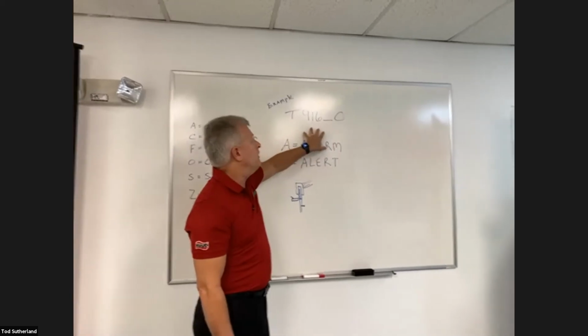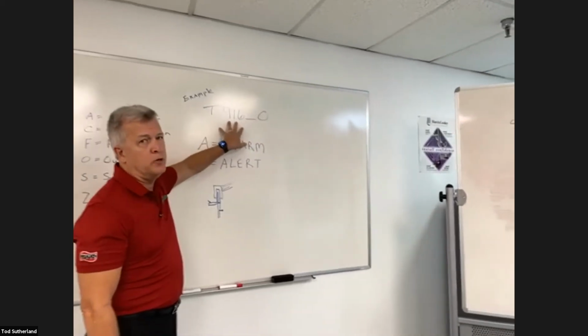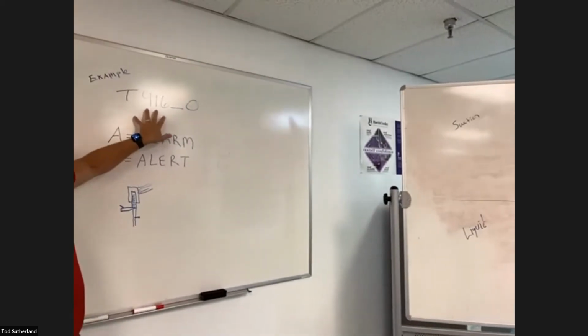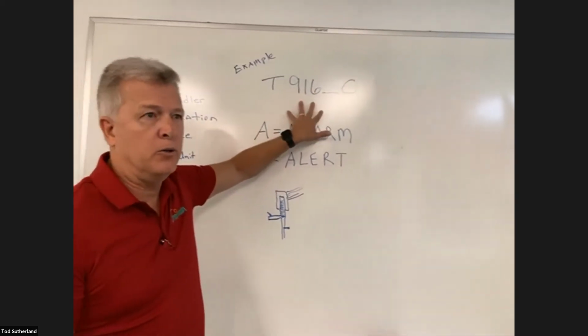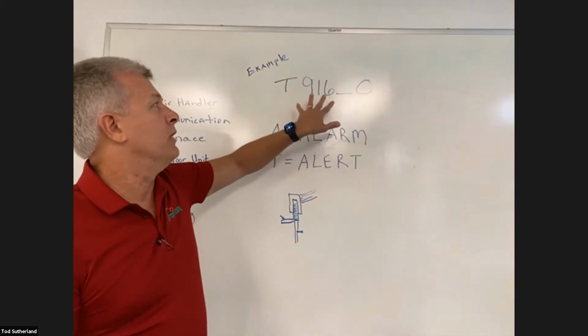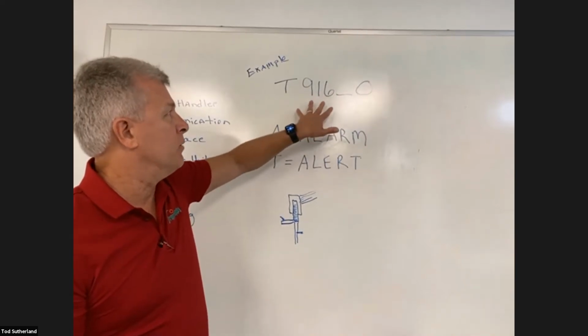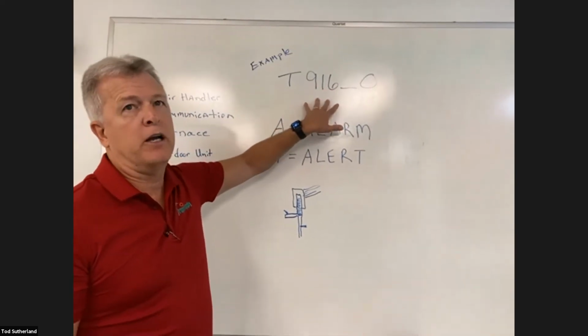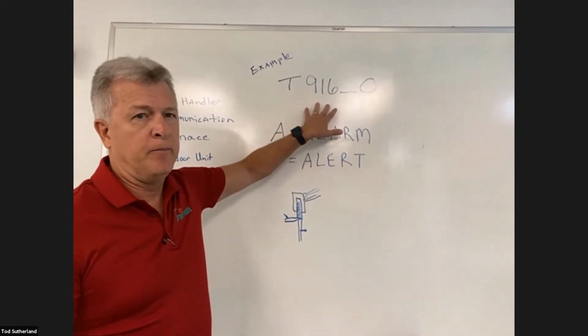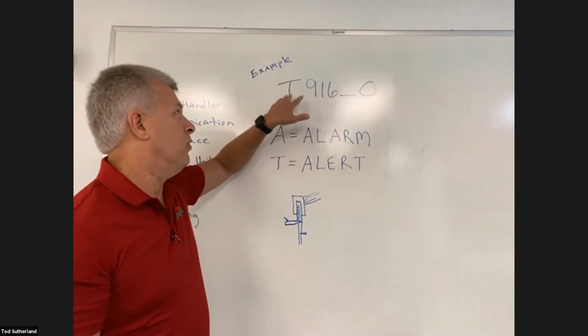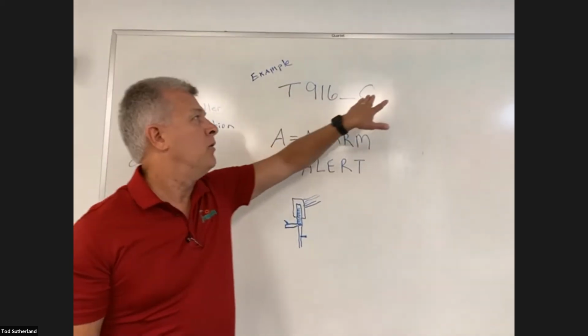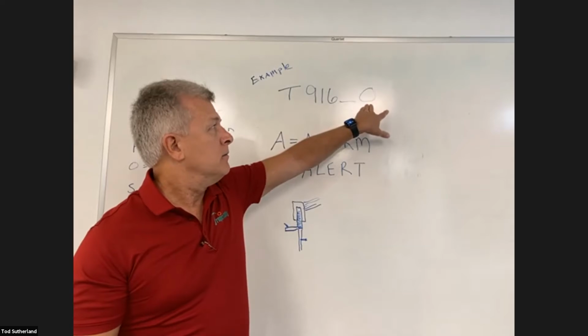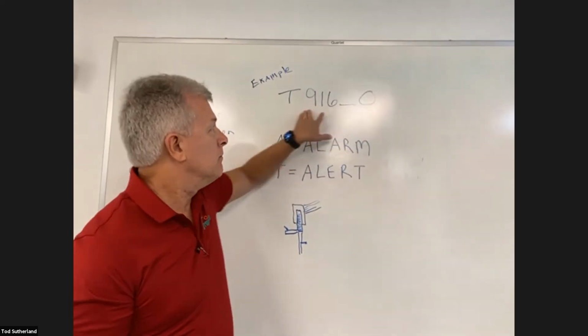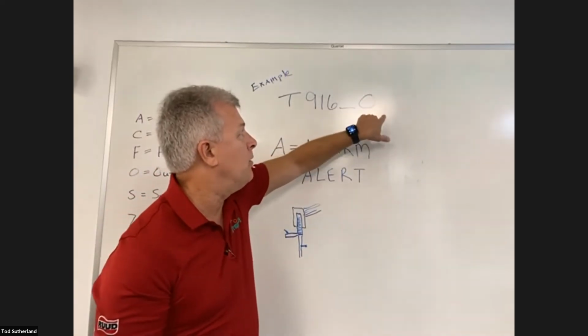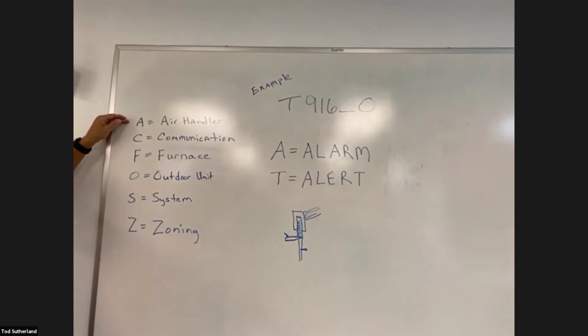It's very important when you're sending these codes to us, to help you diagnose what's going on with the system, that you give us the whole code. A lot of times somebody will call in and we'll say, what's your error code? And they'll say, oh, it was a 916 error code. Well, we don't know if it was an alarm or an alert, and we don't know where it went to. This, at the end of the code here, this _O, this is what that refers to.